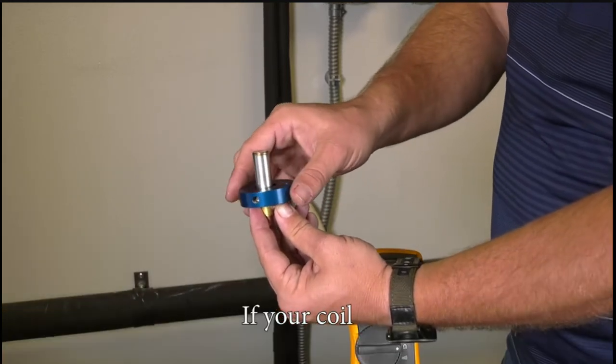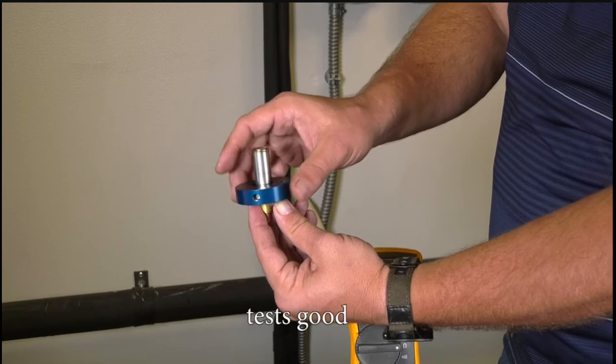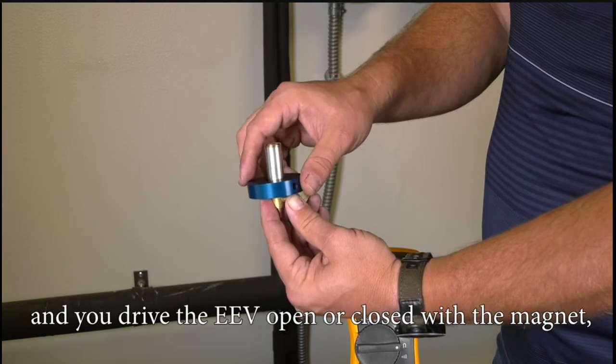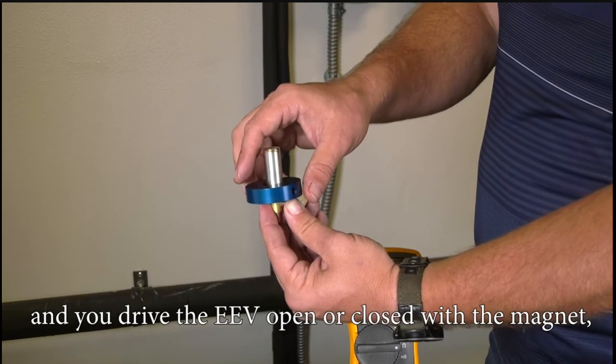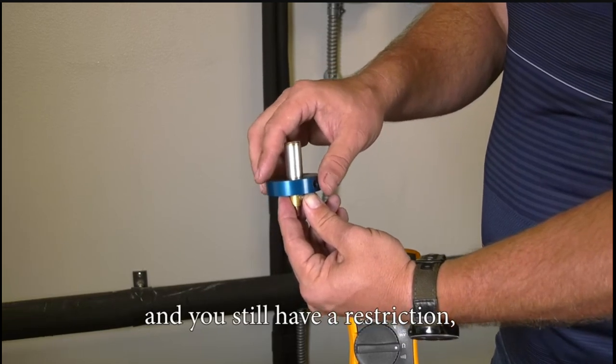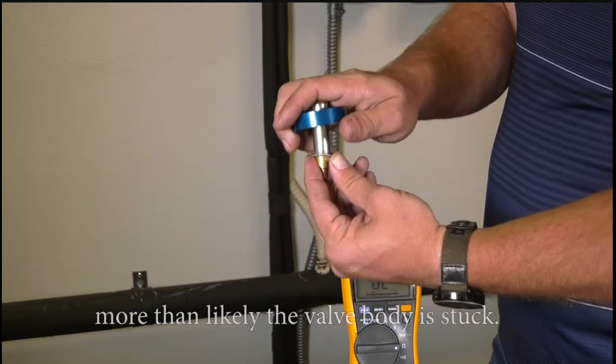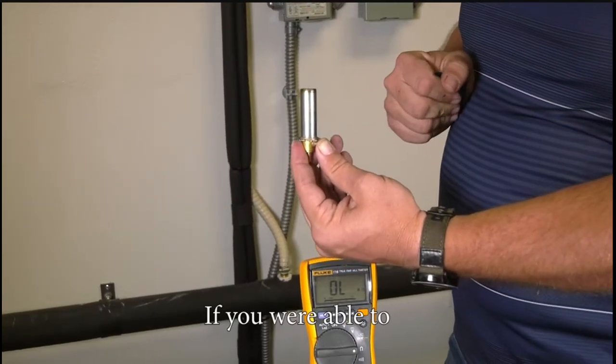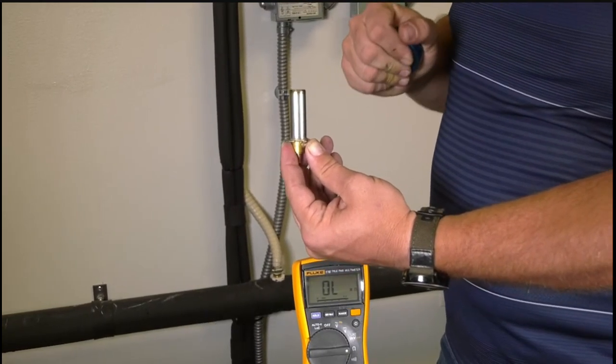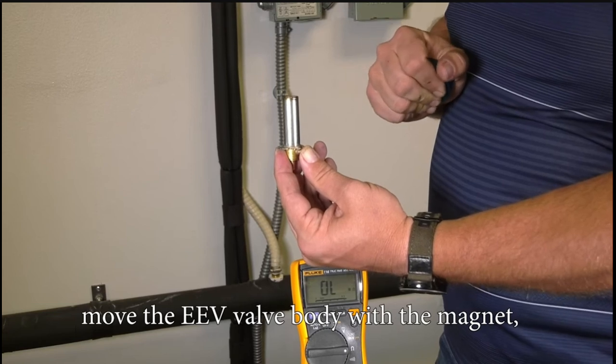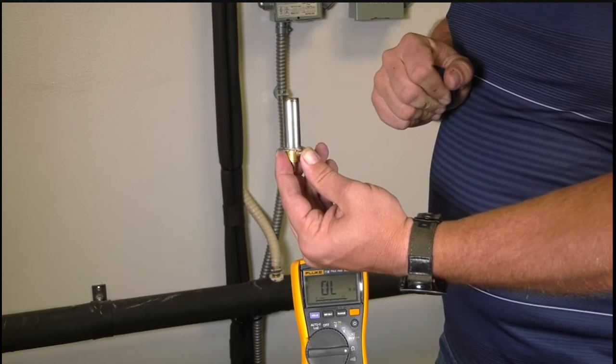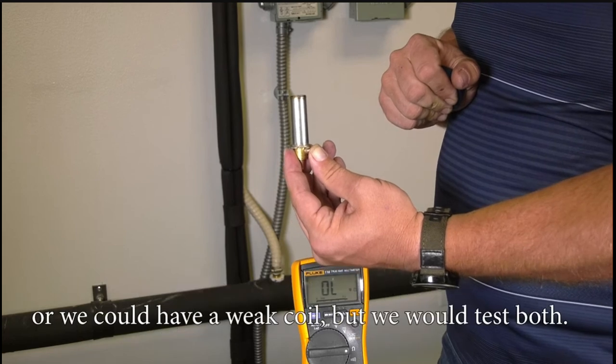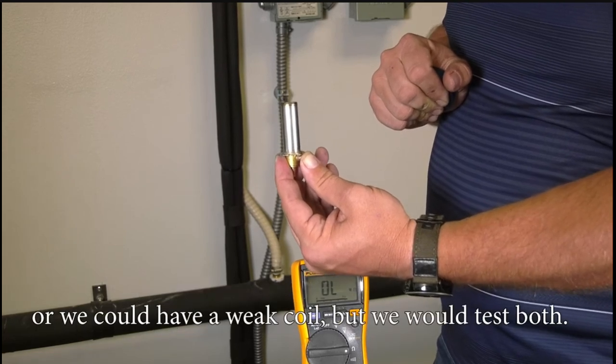If your coil tests good and you drive the EEV open or close with the magnet and you're still having a restriction, more than likely the valve body is stuck. If you were able to move the EEV valve body with the magnet, it could be something else down the line that could be restricting it, or we could have a weak coil, but we would test both.